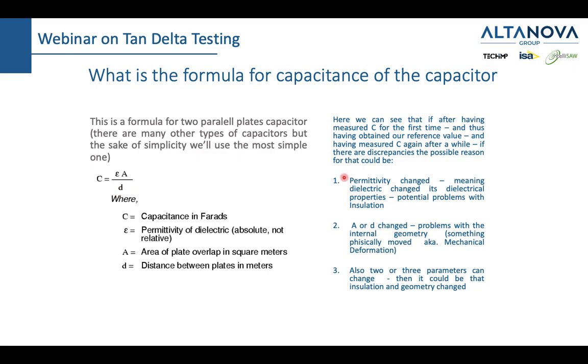So we can have a permittivity which changes, which would constitute a problem with our insulation, or we can have A and D changing, which in turn would mean something else. It could mean that something physically moved inside, or maybe all of them can change. Maybe we have bad insulation due to, let's say, gases inside, and something physically moved, so that's why the capacitance changed. So if the transformer was produced in a factory, and the initial measurement was done, and we got, let's say, 5 nanofarad, and 5 years later we measure again the parasitic capacitance, as we called it, and we get not 5 but 7 nanofarad, then we know that there is quite a lot of change inside of our transformer. Actually, it could be insulation, or it could be something else. It could be physical movement which happened inside.